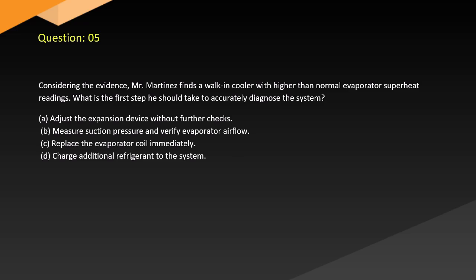Question 5. Considering the evidence, Mr. Martinez finds a walk-in cooler with higher than normal evaporator superheat readings. What is the first step he should take to accurately diagnose the system? A. Adjust the expansion device without further checks. B. Measure suction pressure and verify evaporator airflow. C. Replace the evaporator coil immediately. D. Charge additional refrigerant to the system.